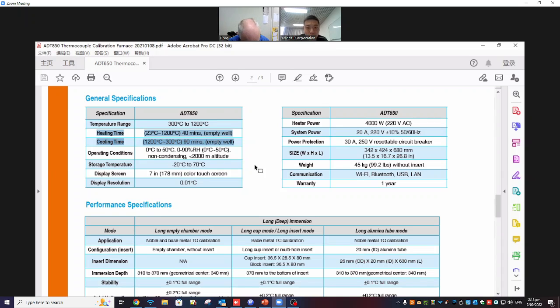This is actually the range for the uniformity and stability specification guarantee. It doesn't mean the temperature of the furnace cannot go below 300 degrees Celsius. You can still set the temperature to like 50 degrees Celsius, which means you can cool the furnace faster to room temperature. But all the specifications, like the uniformity and stability, are guaranteed only within the range of 300 to 1200 degrees Celsius. Sure. Okay.